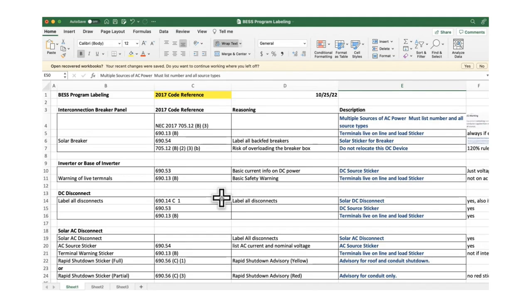And I like the emergency shutoff switch when it's available because I can turn this one knob and I can cause the inverter to go off. I can cause rapid shutdown to happen. I can have the DC shut off from the batteries or whatever. Then have the main panel go dead. And that's nice, but I don't know if that's available in all cases.